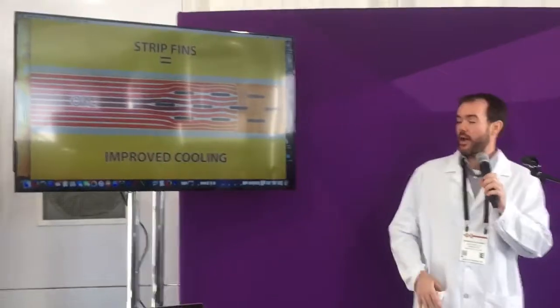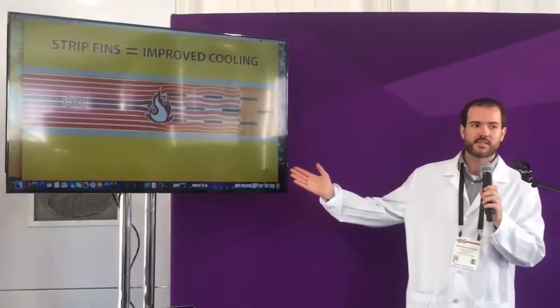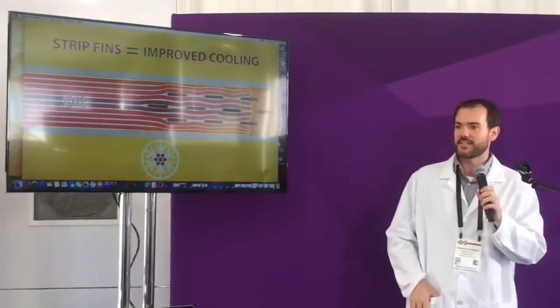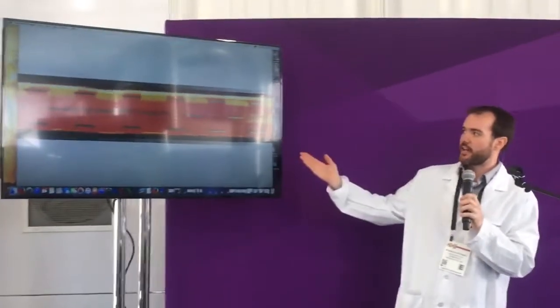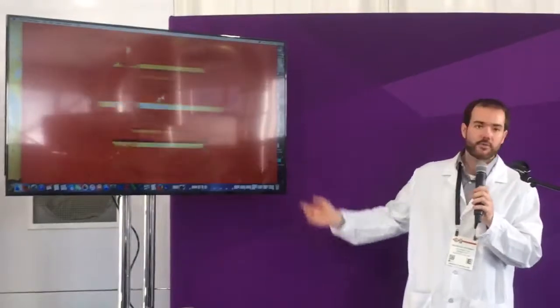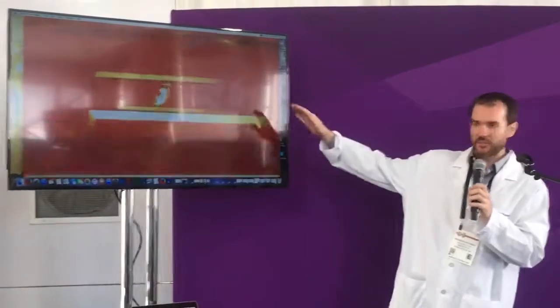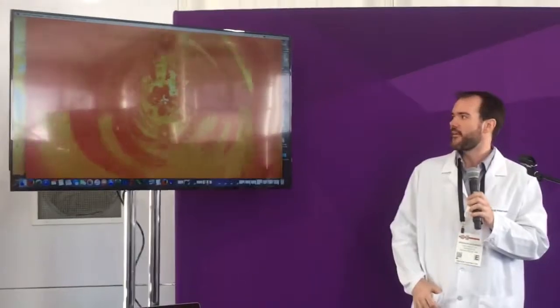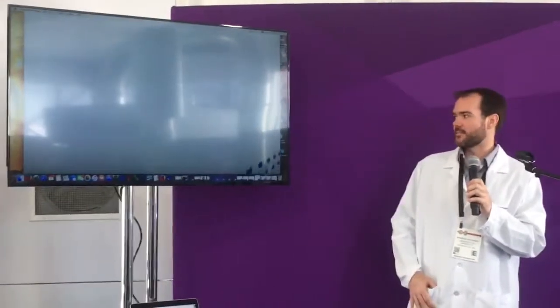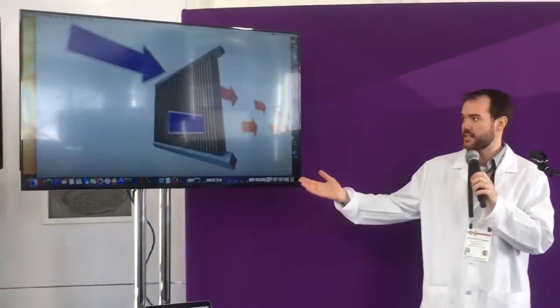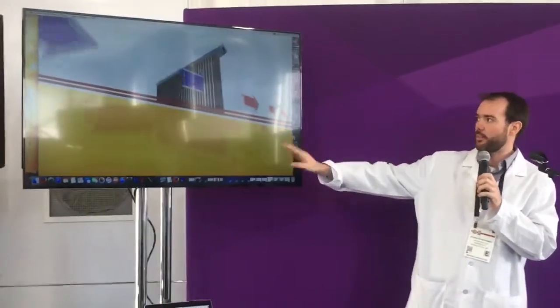Now feel free also, if you have any questions about the process as it's going on, to chime in. We'll answer as we can. The other interesting aspects, aside from the internal features, are the external features of our oil cooler, which, once we finish passing through the offset strip fins here visually, we'll show you the air side and what we've done for that. There we go, and exit it. Now here we see the external flow, so the other side of our heat exchange system. Air needs to be drawn through our heat exchanger, and we need to maximize the external surface area.